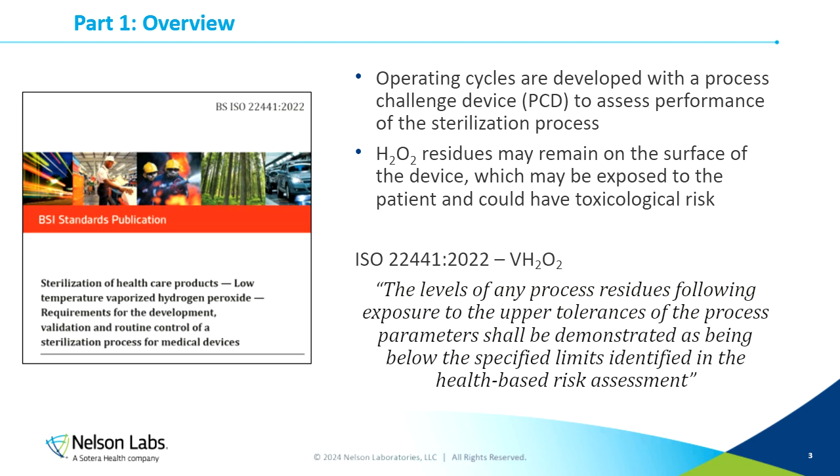It makes sense. We want to see what happens if we expose the device to the upper tolerances of the process. So we want to see what the maximum amount of peroxide residues might be on the device, and then compare it to a value that we say is acceptable in a health-based risk assessment.